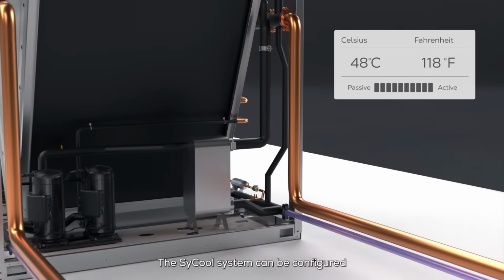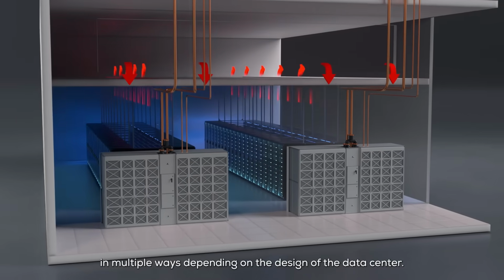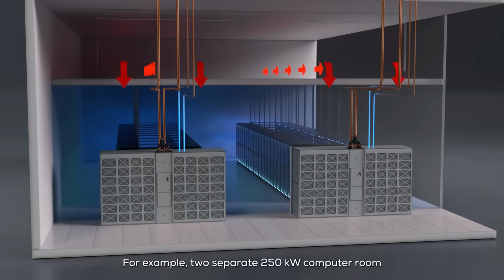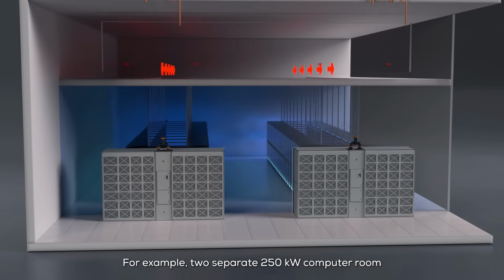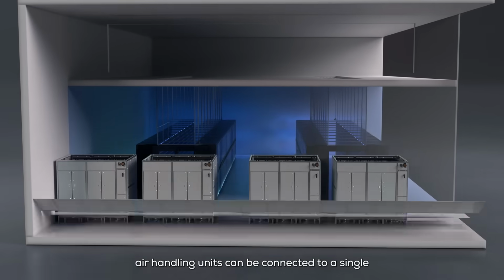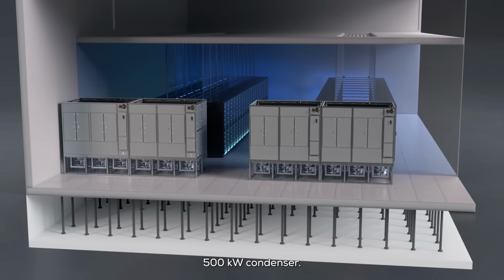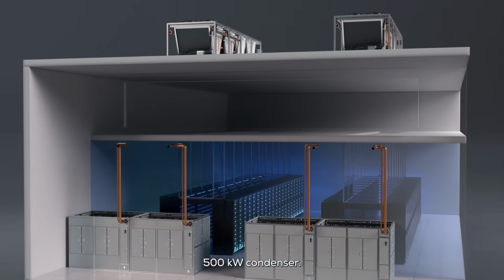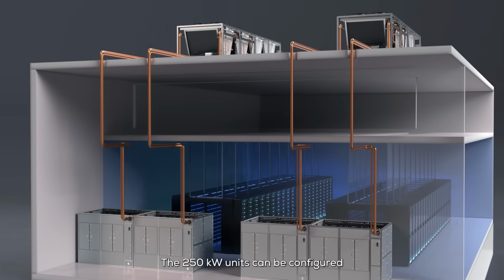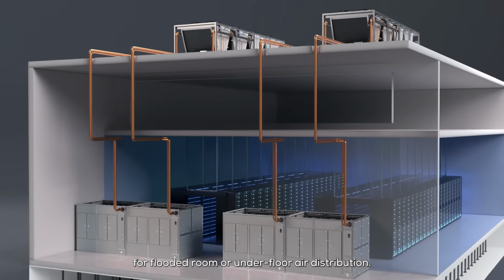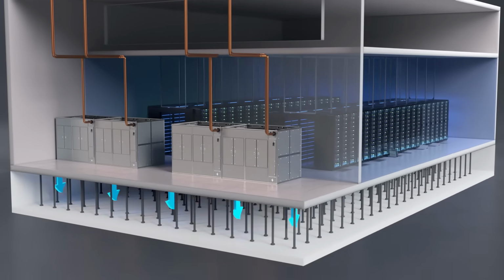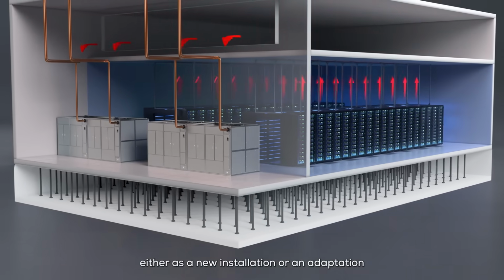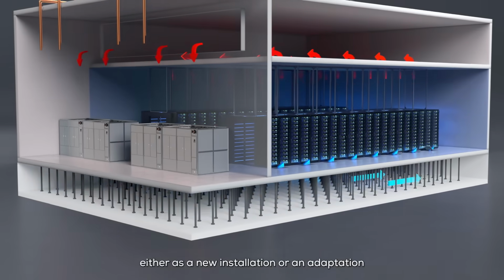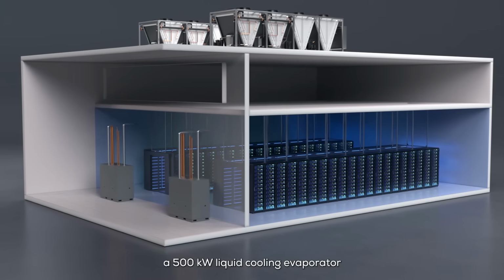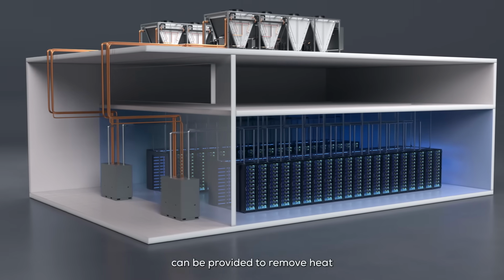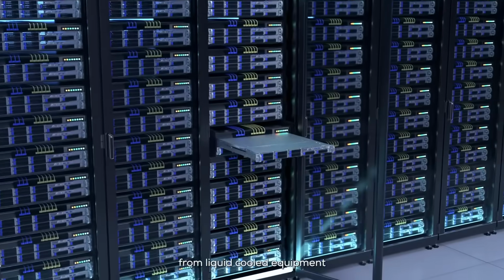The SyCool system can be configured in multiple ways depending on the design of the data center. For example, two separate 250 kilowatt computer room air handling units can be connected to a single 500 kilowatt condenser. The 250 kilowatt units can be configured for flooded room or underfloor air distribution. If liquid cooling is required, either as a new installation or an adaptation from an air-cooled system, a 500 kilowatt liquid cooling evaporator can be provided to remove heat from liquid-cooled equipment.